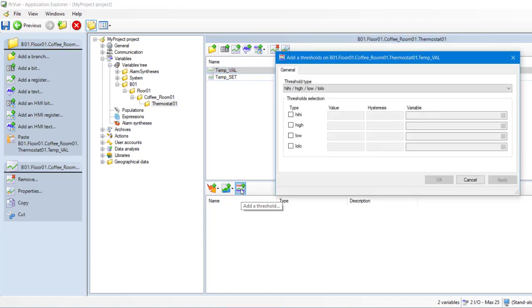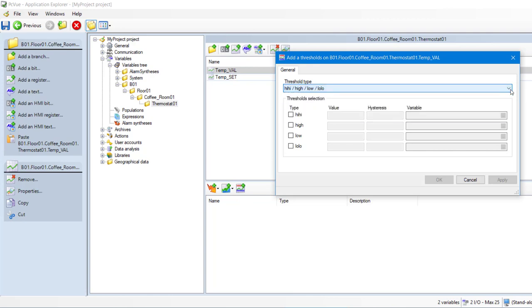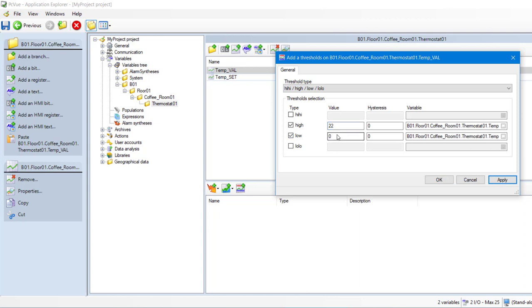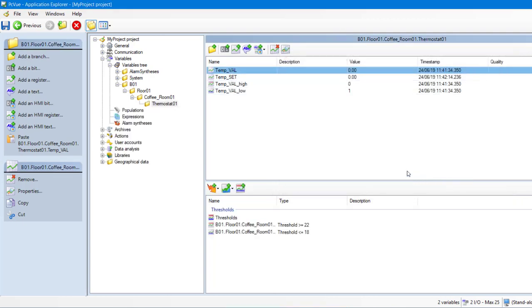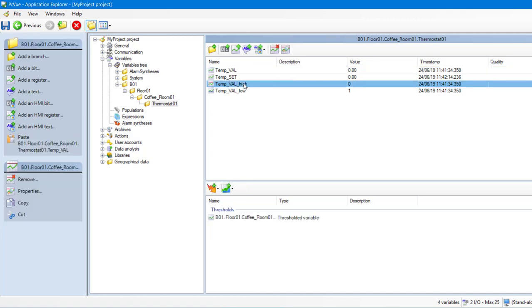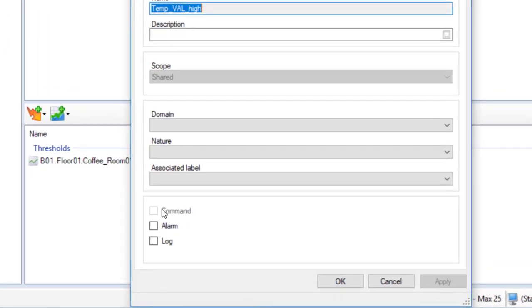Select the type of thresholds. And then, select the threshold high and set the value to 22. And select the threshold low and set the value to 18. Here it is, the variable TempVal is now configured with two thresholds. Now, we need to put an alarm on each threshold. Just double-click on the threshold and select Alarm.